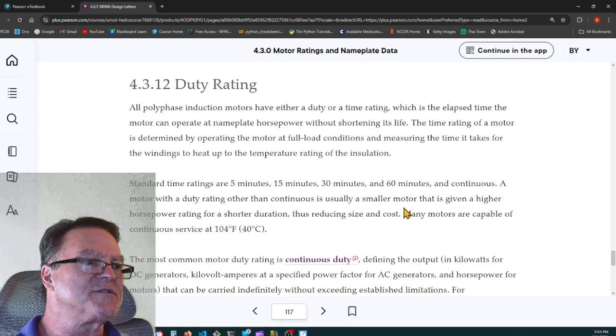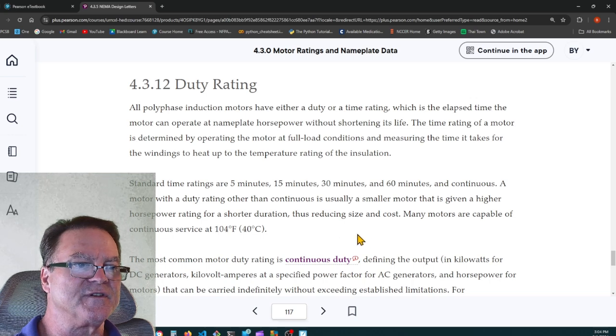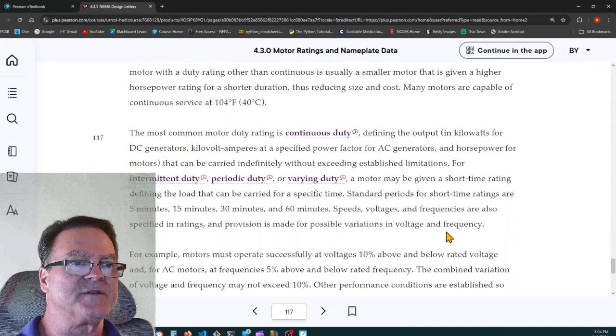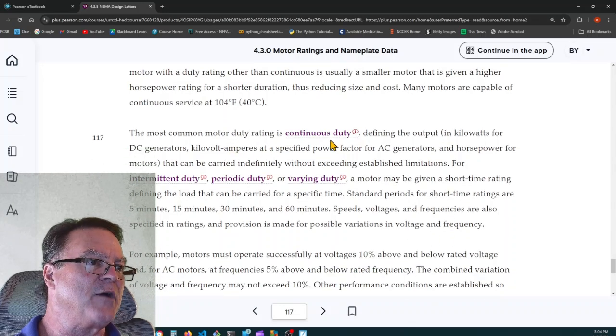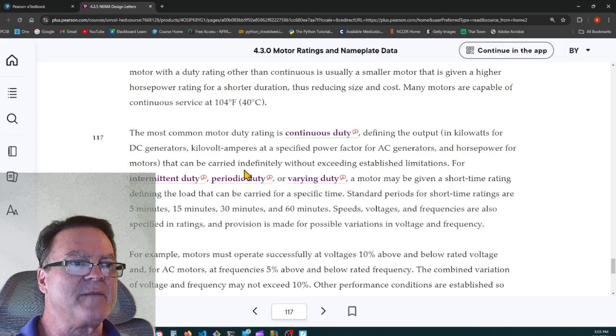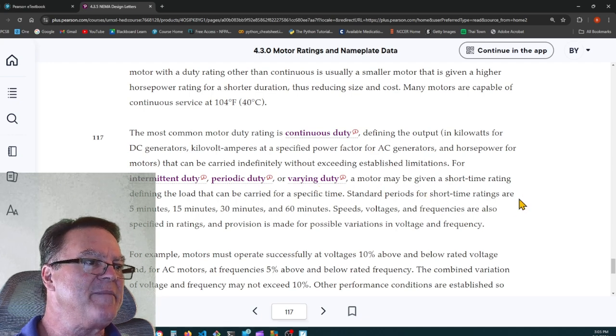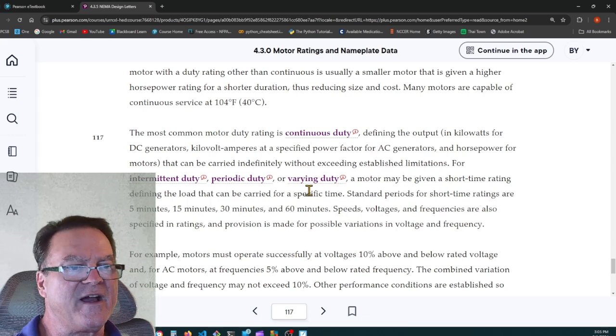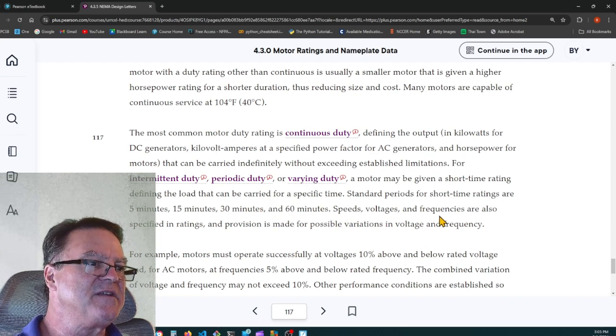A motor with a duty rating other than continuous is usually a smaller motor that's given a higher horsepower rating for a shorter duration, thus reducing the size and cost. Many motors are capable of continuous service at 104 degrees Fahrenheit, 40 degrees Celsius. The most common motor duty rating is continuous duty, defining the output in kilowatts for DC generators, kilovolt amps at a specified power factor for AC generators, and horsepower for motors, that can be carried indefinitely without exceeding established limitations. For intermittent duty, periodic duty, or varying duty, a motor may be given a short time rating defining the load that can be carried for a specific time. Standard periods of short time ratings are 5 minutes, 15 minutes, 30 minutes, and 60 minutes. Speeds, voltages, and frequencies are also specified in ratings, and provision is made for possible variations in voltage and frequency.